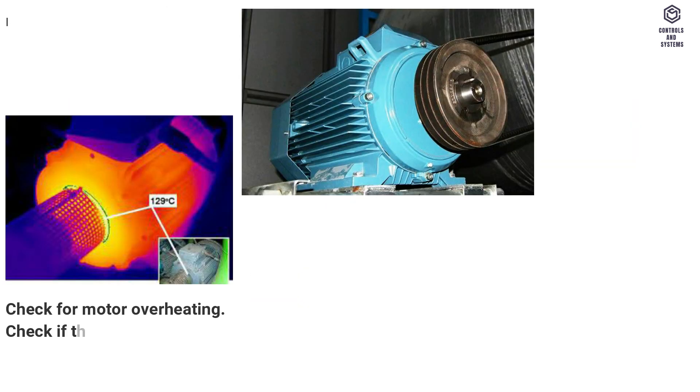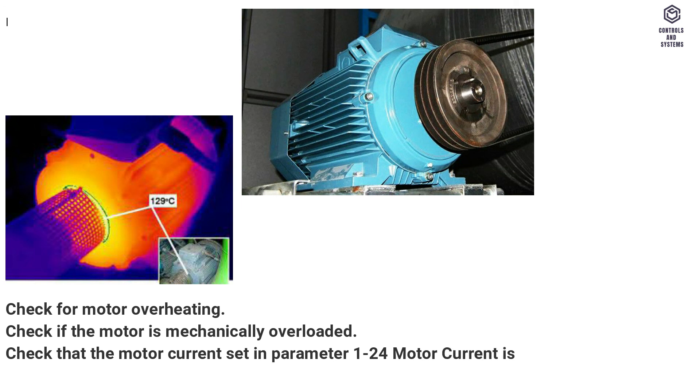Troubleshooting methods: Check for motor overheating. Check if the motor is mechanically overloaded. Check that the motor current set in parameter 1-24 Motor Current is correct.